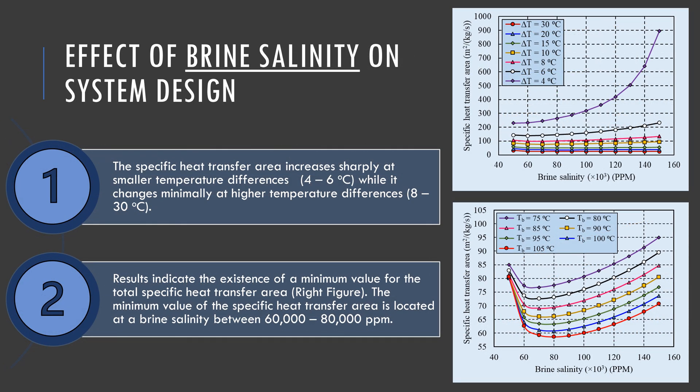Another important factor is the salinity of the discharged brine, which has a significant effect on the specific heat transfer area of the system. As brine salinity increases, the total specific area increases as well, especially for small temperature lifts between 4 to 6 degrees Celsius. Controlling the brine boiling temperature TB between 75 and 105 degrees Celsius results in a minimum value for the specific heat transfer area for every brine boiling temperature. The minimum value occurs for brine salinities between 60,000 and 80,000 ppm.